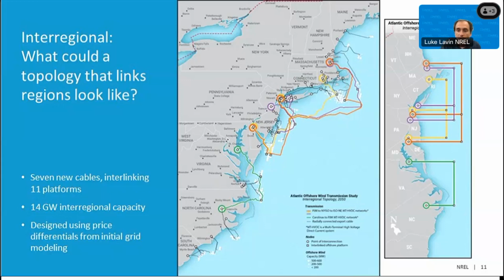Each network is assumed to use multi-terminal high voltage direct current technology with a 525 kilovolt bipole design, and 2 gigawatts is the rated capacity of each of those 7 lines. The choice of that technology is based on what is currently being designed, procured, and built in Europe, and could form the basis of a standard design used in North American projects too.